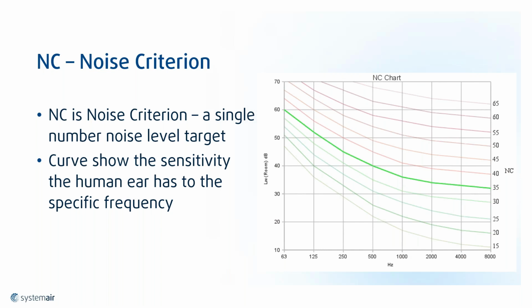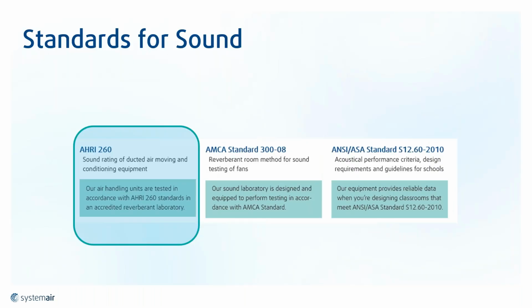That's more for troubleshooting. So what we did was take our Changeair unit and start developing this in California, because they had a very low threshold for sound. So we worked on 3 main standards for sound. First was AHRI 260, and what that covers is ducted air moving and conditioning equipment, how to measure equipment for ducted air movement.